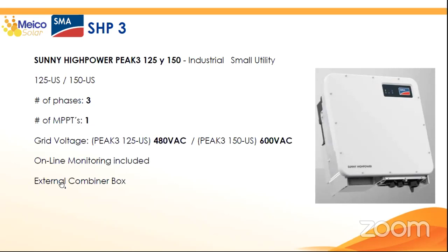It's even an advantage. You also have the online monitoring included with this inverter, but in this one, you need an external combiner box, as you can see here. So this is the connection diagram of the SHP3. You have the inverters, and you have to connect them with cable in this case. So it's a daisy chain, you don't have to close the loop. You only have to connect them one to each other. And from the last one, you can go directly to the data manager. And from the data manager, you can go to the router, okay?